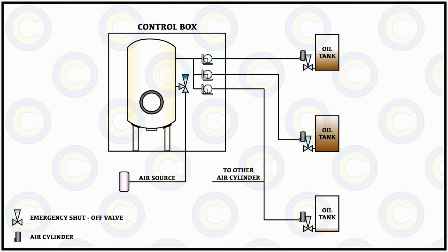So let's say, for example, the service tank as well as the cylinder lubrication tank and other tanks which are continuously under use, because you don't want your pumps to starve, because your vessel is always operational and you can't stop your vessel for testing this. So we are always standby over there, and as soon as the operation happens, we immediately manually reset it and make sure that there is no failure of other mechanisms that happen while testing the quick closing valves.